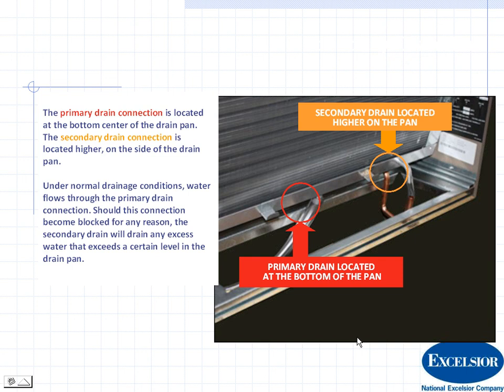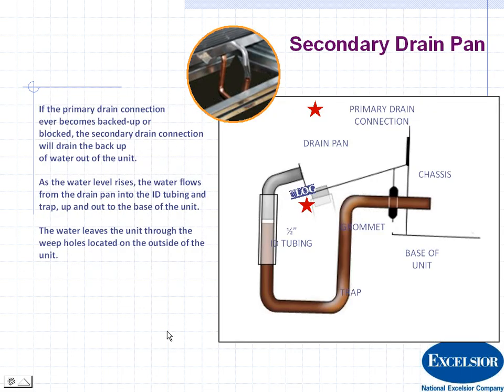It also has one of the nice features about this Magic Pack, I'm sorry, the CPG that others don't have, is a secondary drain. You wouldn't want the primary drain to get clogged and have water running all over a patio, leaking down to other people, or if this is inside, you wouldn't want to have water running into the conditioned space, because these units are obviously not in basements with drains. So one of the nice things is that this unit has a secondary condensate drain for you, and that will catch any water as it drains out.